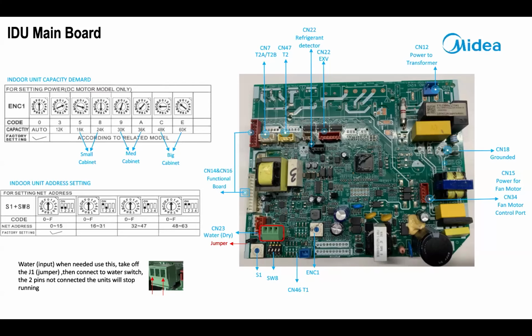All right, CN12 is power to the transformer. 18 is a ground. 15 says power for the fan motor, but actually that is the control voltage for the fan motor. That is sent to the fan driver board, and then the fan driver powers both. ENC1 is a capacity selection. This should come out of the box. You should not have to mess with it. When it comes out of the box, you're probably going to notice it's got about a half stick of hot glue on it. That's so you don't mess with it. CN46 is your T1 sensor.